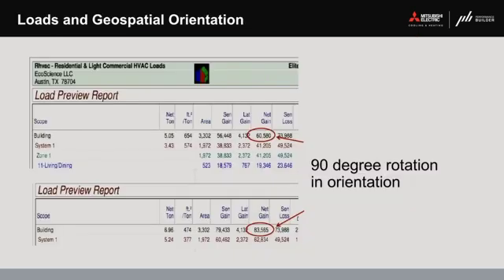This is a snippet of a load preview report, where we summarize the various loads of different rooms and zones of a house. Here I've shown the exact same building—if you look at the area, 3302 for the top and 3302 for the bottom, that's the same building, just rotated 90 degrees. That rotation has made a 2-ton difference in the cooling load. So for a top takeaway: getting the orientation for that building correct can be critically important, especially if a building has a lot of glass.